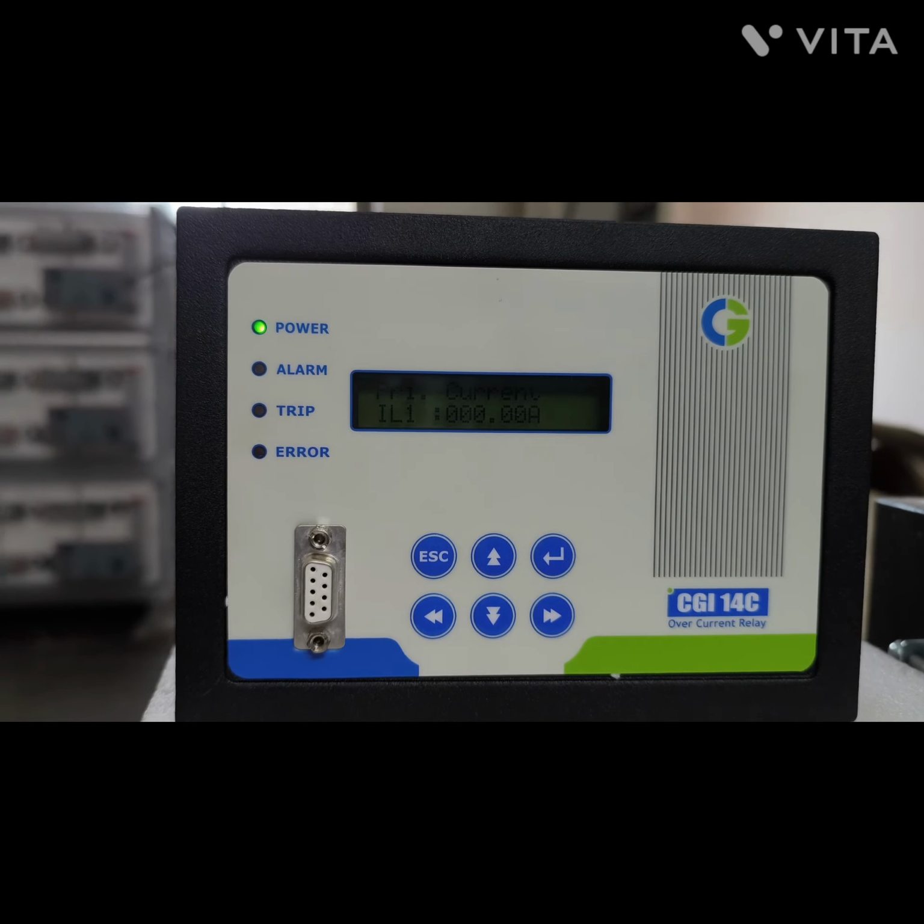So 80% under voltage and 110% or 115% over voltage is there. In NDR setting, generally we are giving 3 to 20 volts. That we can see here, go down to this protection, and if you go down here, 15 volt is there by default, that we can change it. So these are the only 3, particularly over voltage, under voltage and NDR protection, in this particular relay CGB24C.